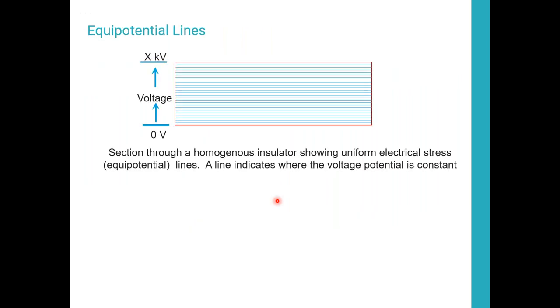The purpose of the insulation in the electric systems we're talking about is basically to evenly distribute the equipotential lines, or the potential electrical stress lines, evenly across the insulation. So you get no concentrations of potential. And we can see up to X kV of voltage drop across this, but these horizontal blue lines are potential lines that are being held evenly spaced, no concentrations.